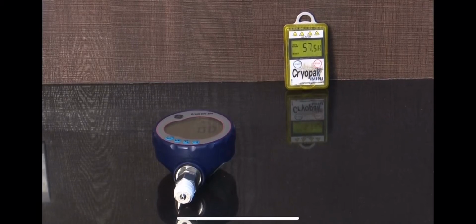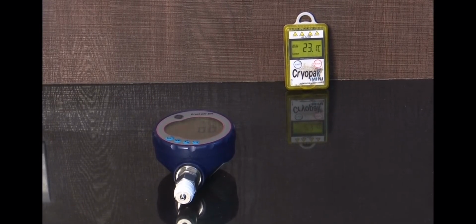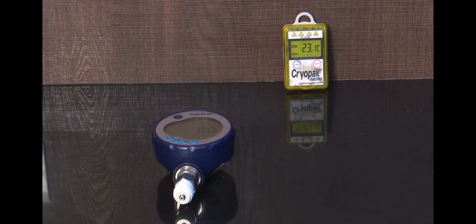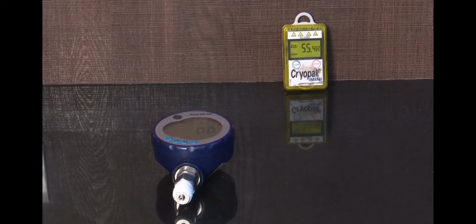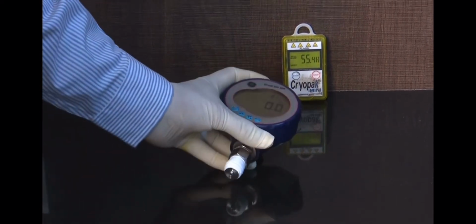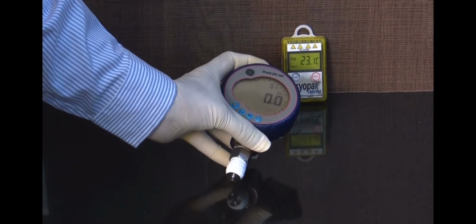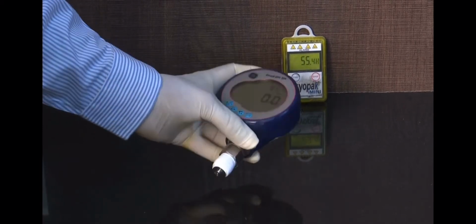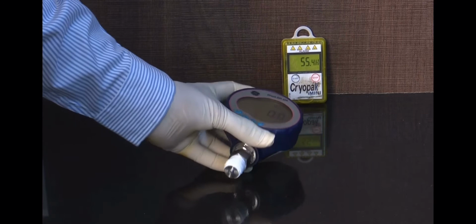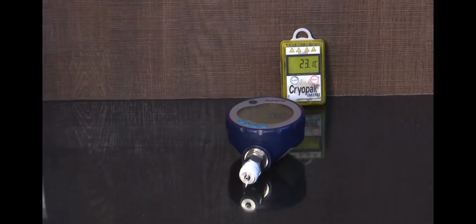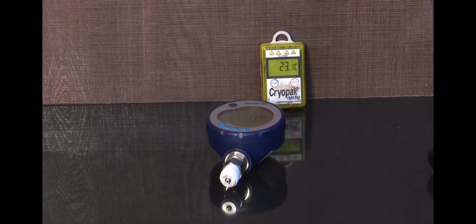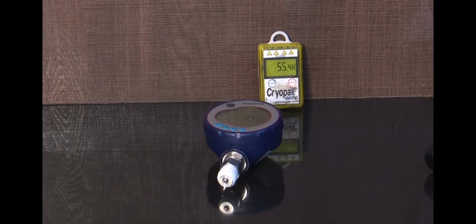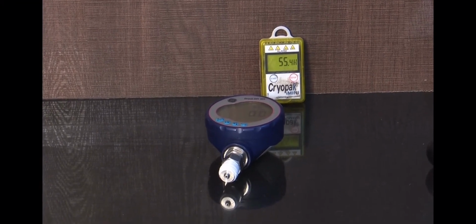I am demonstrating live display of step-by-step calibration method for pressure gauge. After cleaning, visually inspect the pressure gauge for any physical damage. Keep the pressure gauge for at least 30 minutes for soaking at 23 plus minus 1.5 degrees centigrade so that the temperature is brought to equilibrium.